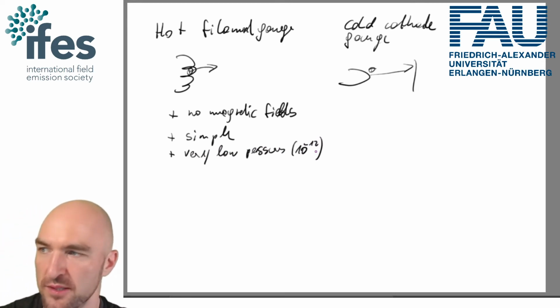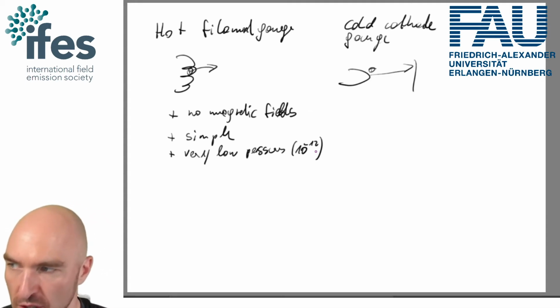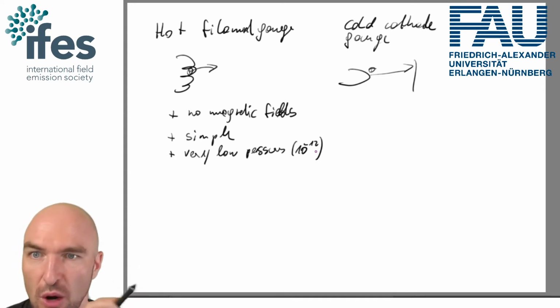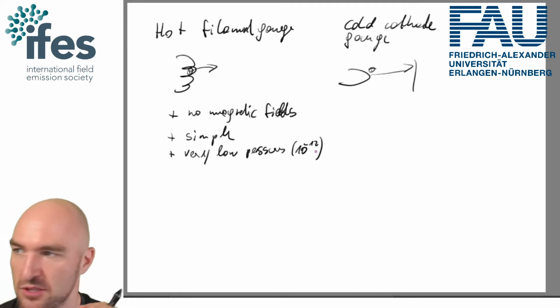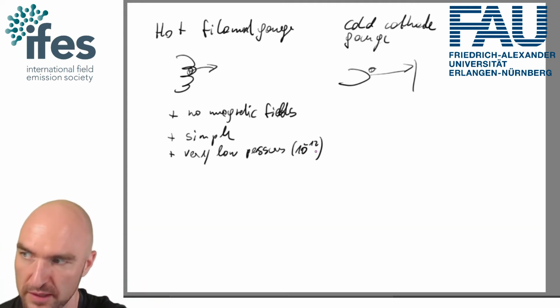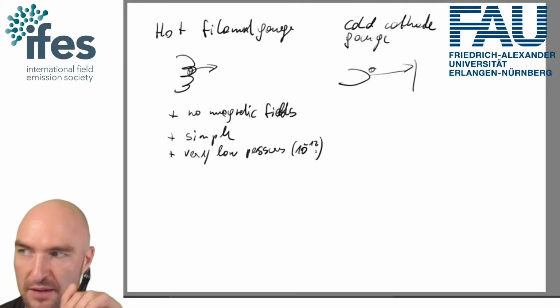If you go to physicists that, for example, do antimatter experiments, atomic clocks and the like, that really have extremely good vacuums, they have no way apart from the experiment itself to measure the pressure. So they don't have any of those gauges anymore at all. This is just a gauge, meaning I plonk that thing onto my system and it gives me a pressure reading. In many other cases, I have nothing but the experiment to tell me what the pressure is. And there are special versions of the hot filament gauge that can get us down to 10 to the minus 12 millibars, which is very good.